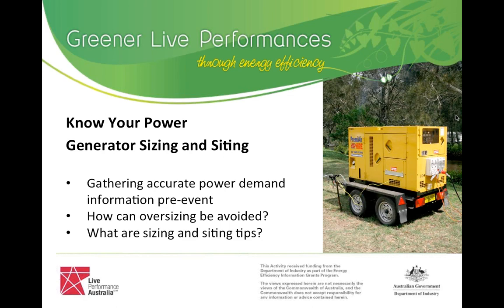Now we have Stephen from Coates Hire on the line. What we're discussing is how generator companies receive information from event managers in order to make accurate and efficient estimations on generator sizing. Our best work is when we work closely with event organisers around where to position generators. We offer a service to advise on the lowest amount of cable to be used — obviously where your biggest load is, you put your biggest generator — and try to distribute from there, limiting the cable run to avoid voltage drop.